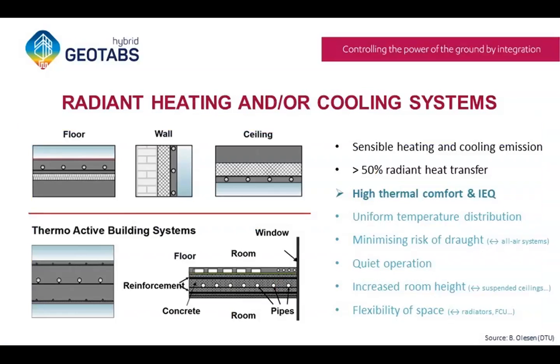TABS is an example of a radiant heating and/or cooling system. These systems provide sensible heating and cooling to rooms, where more than 50% of the heat transfer happens via radiation. Such systems are well known for their very high thermal comfort and indoor environmental quality. Some advantages in terms of comfort are the uniform temperature distribution, the minimization of the risk of draught compared to all-air systems, a quiet operation, and, because the system is integrated in the building, an increased room height and flexibility of space.